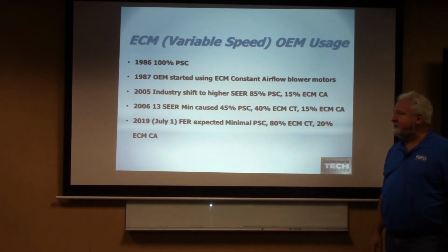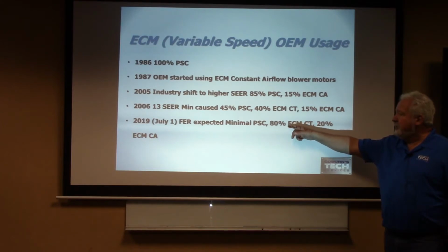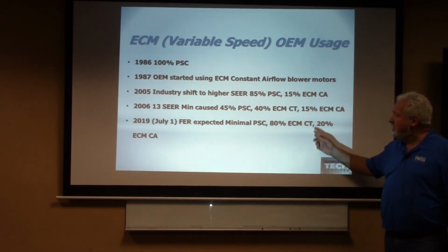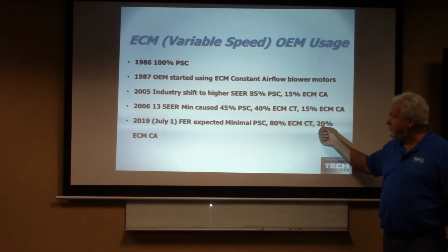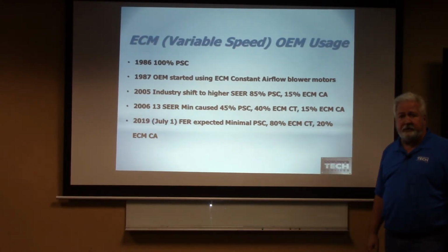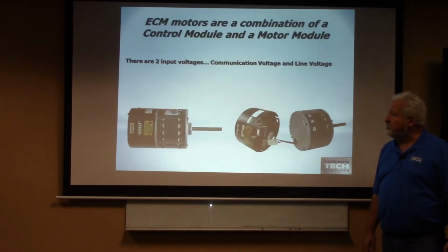On July 1st of 2019, the new efficiency regulation is coming into play, and it's expected that there'll be minimal PSC motors left out there. We'll still see them in some of our air handlers, but on all your gas furnaces, you'll see ECM motors. It's expected to change from 80% PSC to minimal PSCs, 80% ECMs, and 20% CA motors. We'll see just about the whole industry shift over to variable speed motors, that constant torque motor. So if you didn't like them before, understand that's going to be your future. So just be aware of it.